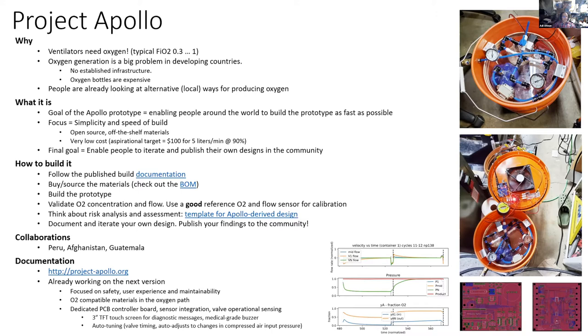To build it, you just follow the published documentation and check out the BOM, checking local sources for your materials. Some materials like zeolites have to be sourced from China, but generally we publish a detailed BOM on how to achieve that. After building a prototype, you have to validate oxygen concentration and flow, and for that you need a good reference oxygen sensor, which is also expensive. Unfortunately, that's the way of life — the quality of your design depends on the quality of your calibration.